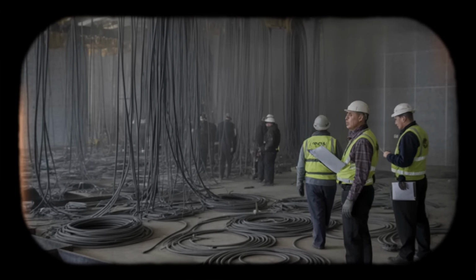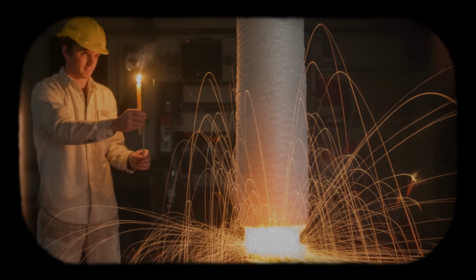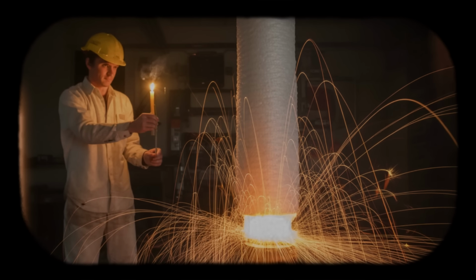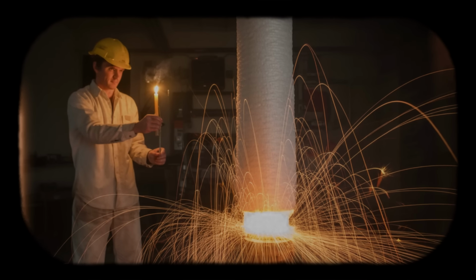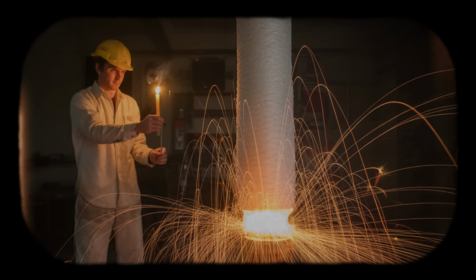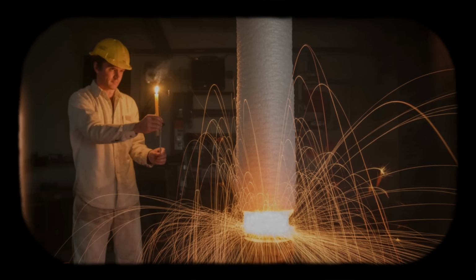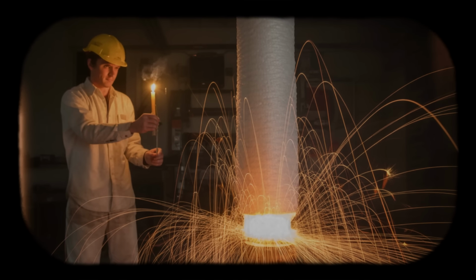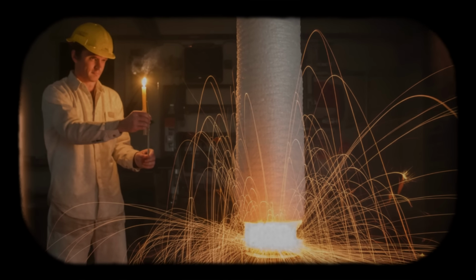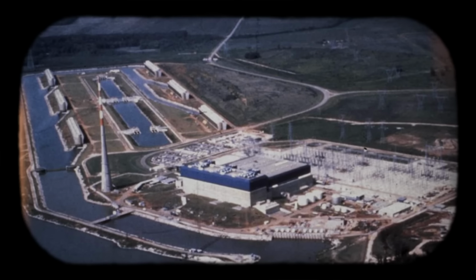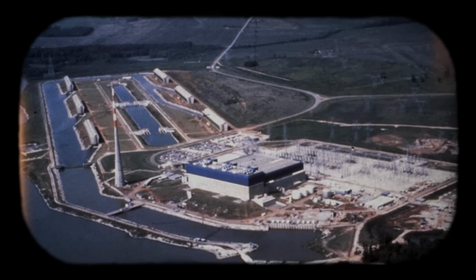The fire revealed fundamental design vulnerabilities. Polyurethane foam penetration seals allowed fire to spread from room to room. Unprotected cable trays provided continuous fuel pathways. Lack of fire barriers between redundant safety trains meant that one fire could disable multiple systems simultaneously. These vulnerabilities exist not just at Browns Ferry but at nuclear plants throughout the United States.